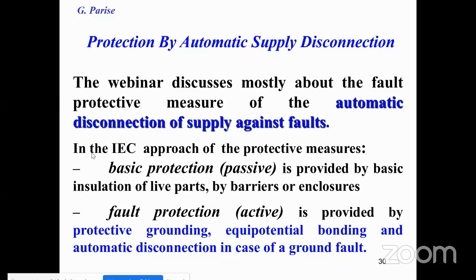This protective measure is an active protection. In fact, in the IEC approach, the basic protection, which is passive, is provided by basic insulation of live parts, by barriers or enclosures. That is, direct contact is not possible. So to avoid direct contact it is necessary to provide basic insulation of live parts, so to have a double insulation of a conductor.